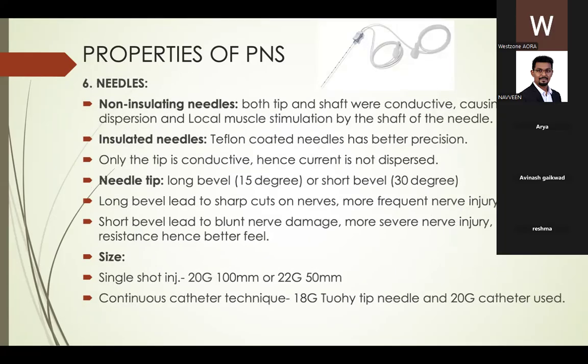Coming to needles, there are non-insulated needles and insulated needles. In non-insulated needles, both the tip and the shaft are conductive, which causes current dispersion and local muscle stimulation by the shaft of the needle. Insulated needles are Teflon coated, which gives better precision because only the tip is conductive, and hence the current is not dispersed. The needle tip can be either a long bevel or a short bevel.